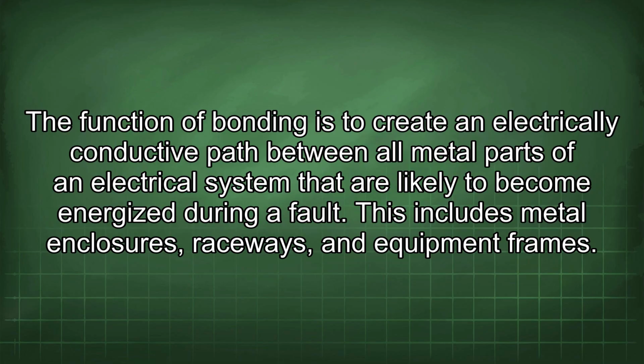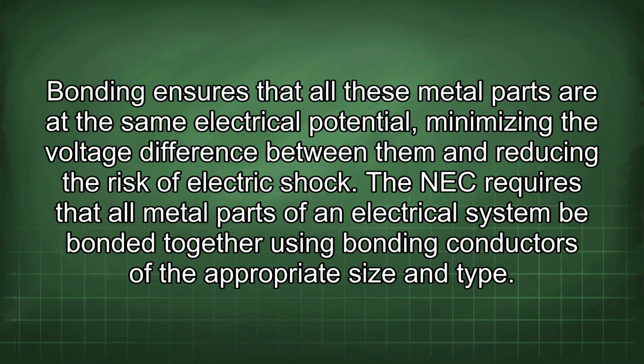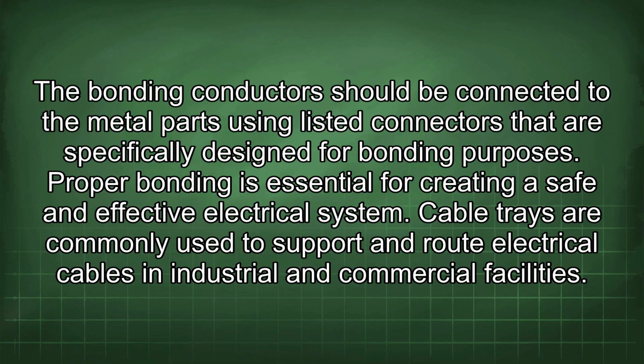The function of bonding is to create an electrically conductive path between all metal parts of an electrical system that are likely to become energized during a fault. This includes metal enclosures, raceways, and equipment frames. Bonding ensures that all these metal parts are at the same electrical potential, minimizing the voltage difference between them and reducing the risk of electric shock. The NEC requires that all metal parts of an electrical system be bonded together using bonding conductors of the appropriate size and type. The bonding conductors should be connected to the metal parts using listed connectors that are specifically designed for bonding purposes. Proper bonding is essential for creating a safe and effective electrical system.